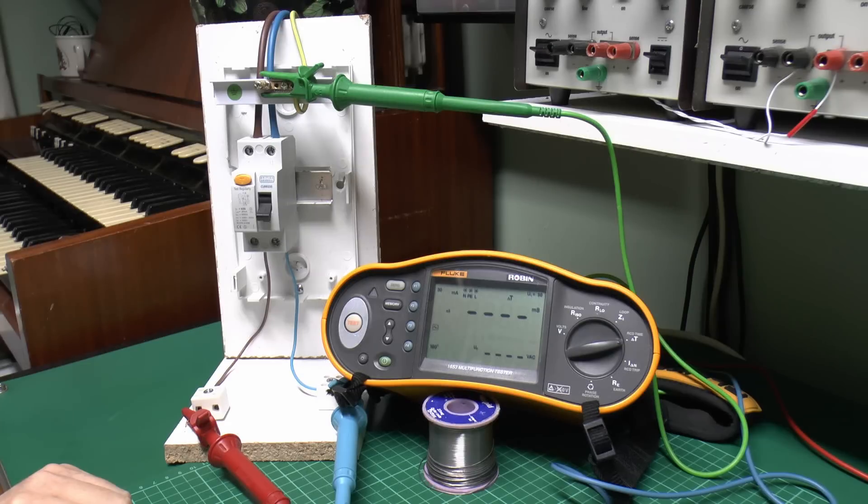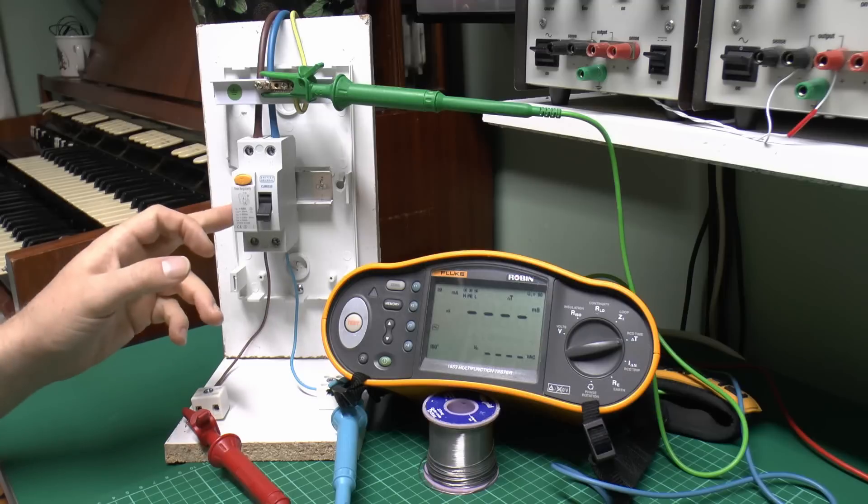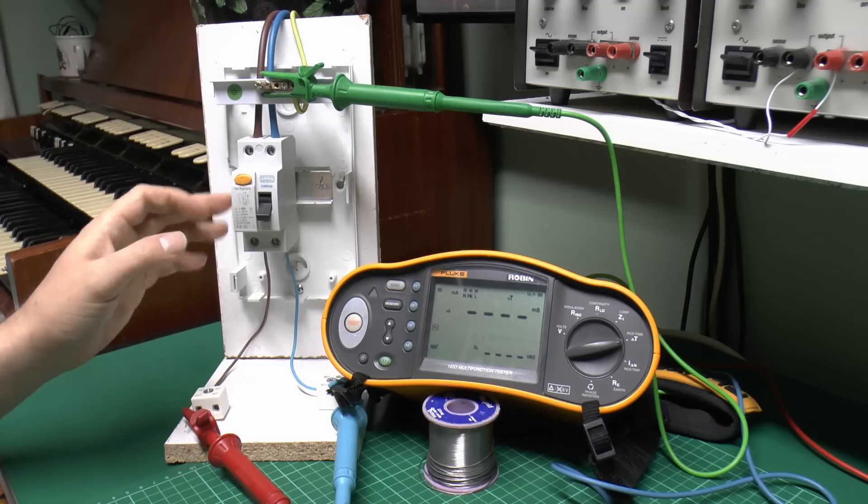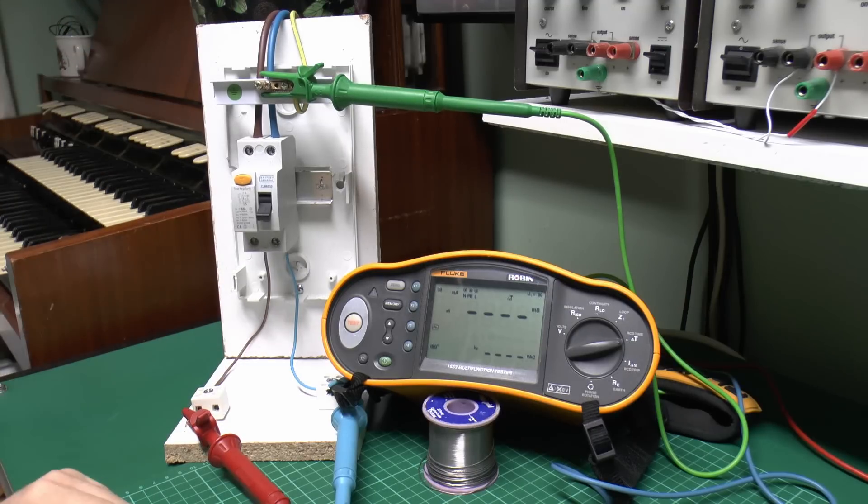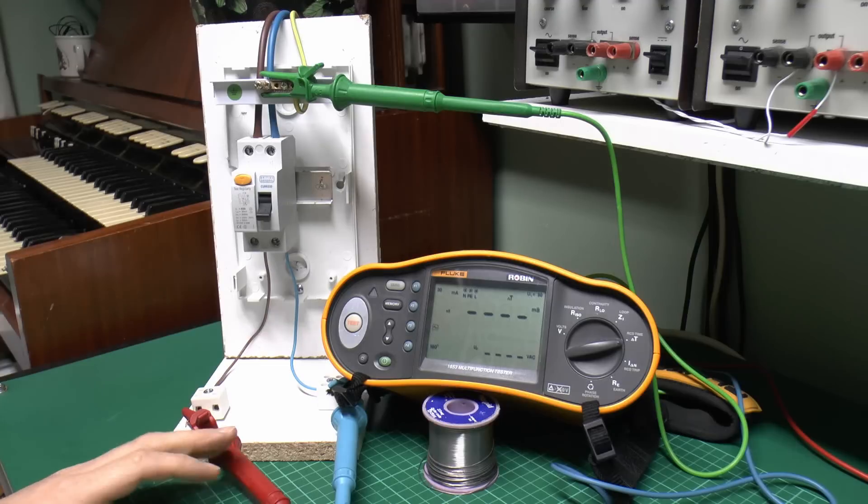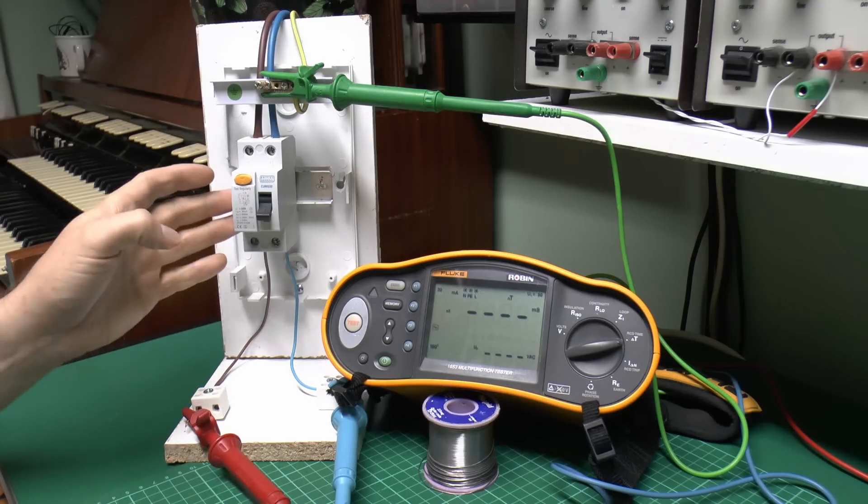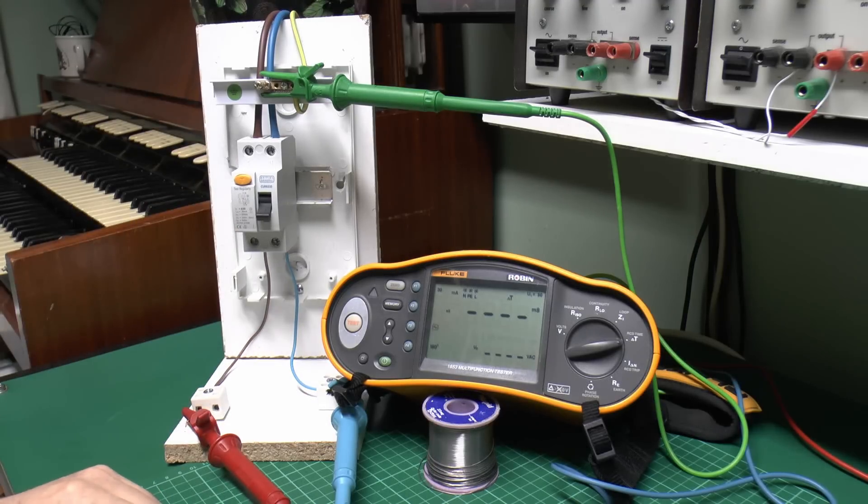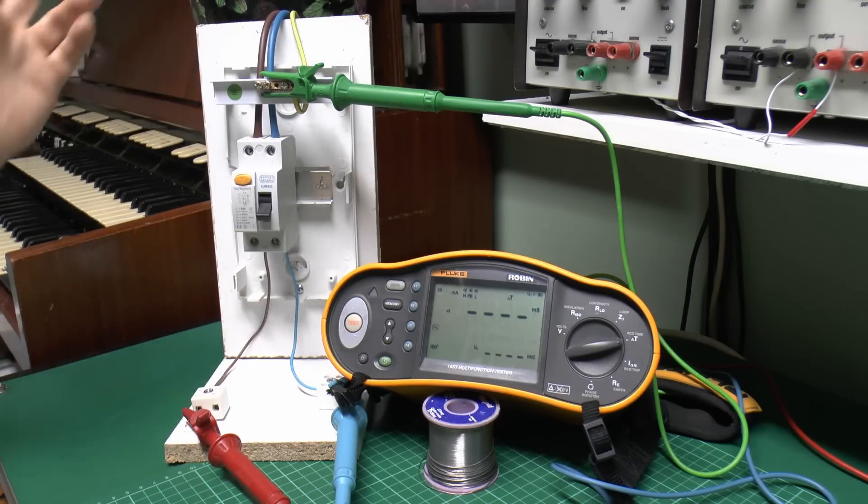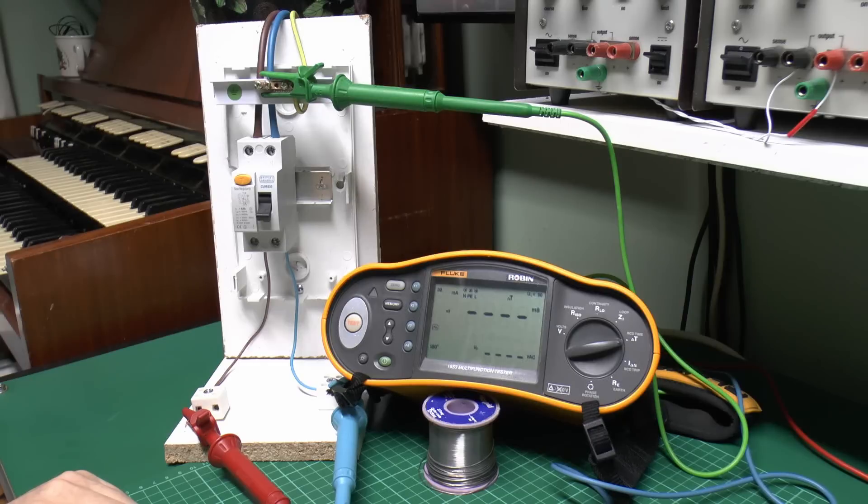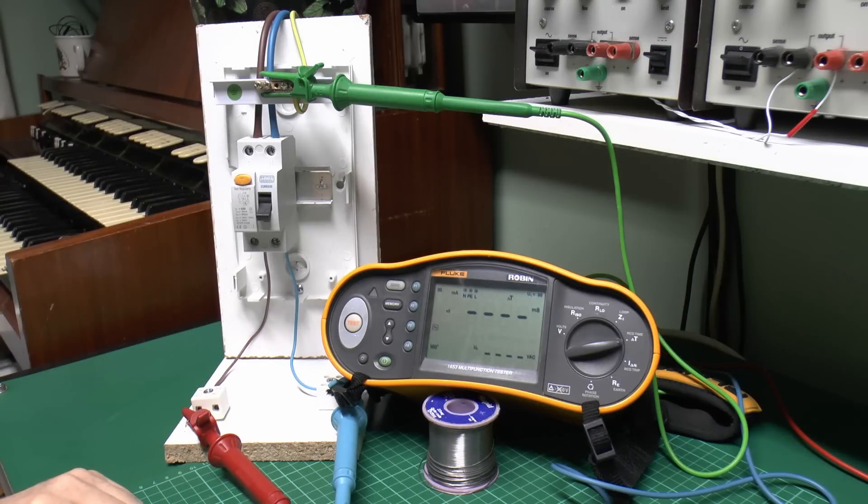However, there are circumstances, particularly in things like caravan parks and other annoying areas, where you actually end up with two RCDs connected, one here and then one further back on the supply, and unfortunately they're quite often the same rating. So that if you attempt to test the RCD here like this, it's quite likely to either trip this one, or it may also trip the one further up the supply line, in which case that's really annoying because then you can't properly test this one at all.